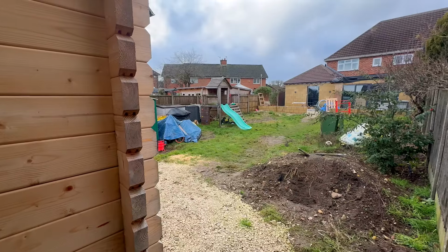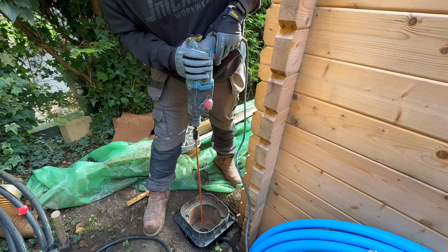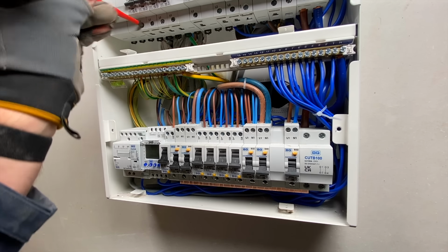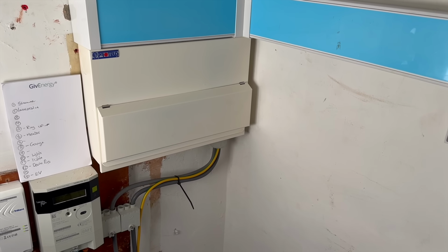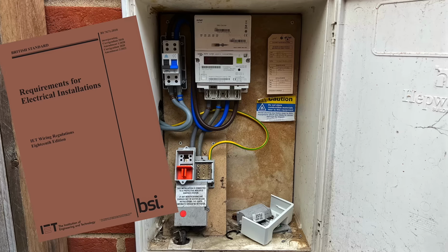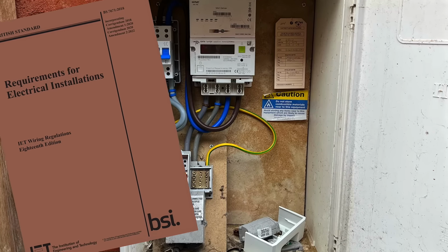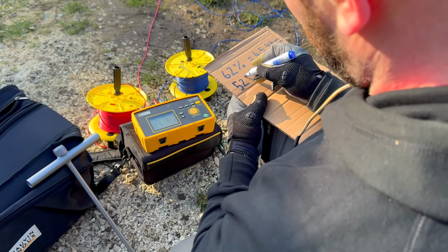In many installations like this, electricians will instinctively install an earth electrode. It feels like the safest option, and it avoids having to think too deeply about the existing installation. But BS7671 doesn't work like that. It requires the earthing and protective measures to be appropriate for that installation. We need to determine what BS7671 actually says, and understand what testing can actually prove.